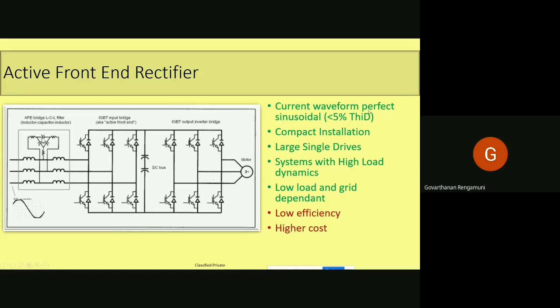By doing this, the current waveform will be maintained perfectly sinusoidal to meet less than 5% total harmonic distortion as prescribed in IEEE 519. Here, there is no retrofit, but it is a part of the drive. So it is a compact installation, and it is used for large single drives, systems with high load dynamics, low load and grid dependent. The only thing is low efficiency, because a lot of switches and the switching losses should also be considered here. And the cost involved is also high because there is an LCL filter at the input side, and there are control circuits also available.